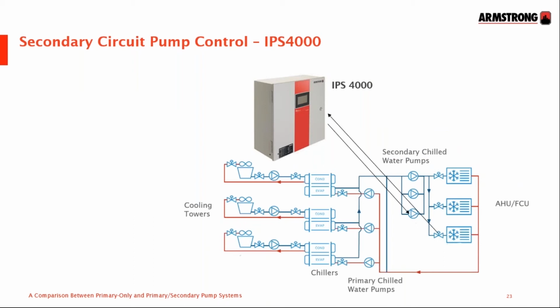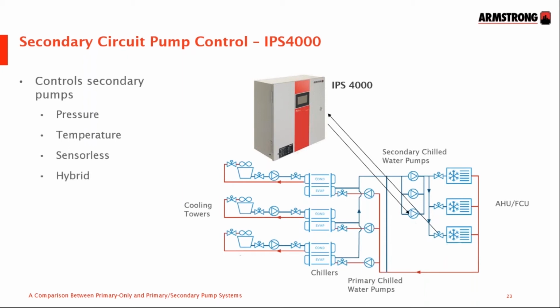Let's have a look then at the IPS 4000, which is specified for variable secondary applications. It stages pumps in and out on a best efficiency basis as per the 4500 and works on the information provided by the sensorless pumps, which tell it the flow rate. It has an embedded sensorless map and an embedded pressure control curve that emulates the response driven by a remotely mounted transducer. But the IPS 4000, like the 4500, can also work with pressure and/or temperature transducers and operate using sensorless as well in hybrid mode, where the transducer takes precedence. Say, for example, it's managing cooling water flow to a server room with the transducer there. That will take precedence and ensure the server gets the cooling all the time. Again, these features are just not available from other manufacturers.